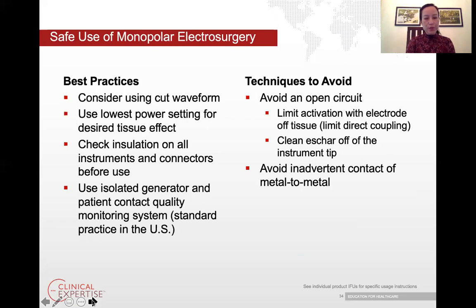Use the lowest power setting possible. Check the insulation on all instruments before use, and avoid an open circuit by not activating an electrode off tissue, and always cleaning the eschar off electrodes.